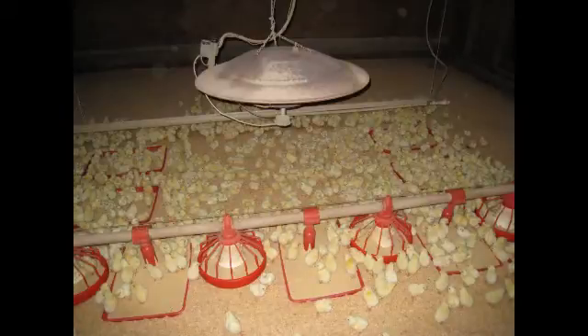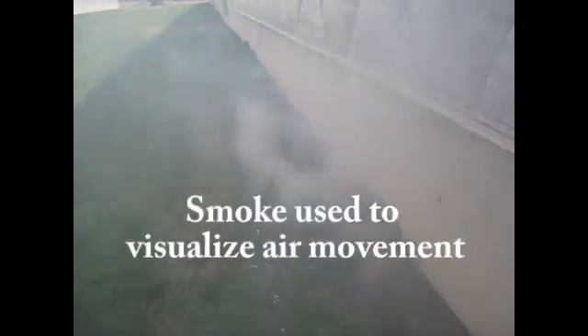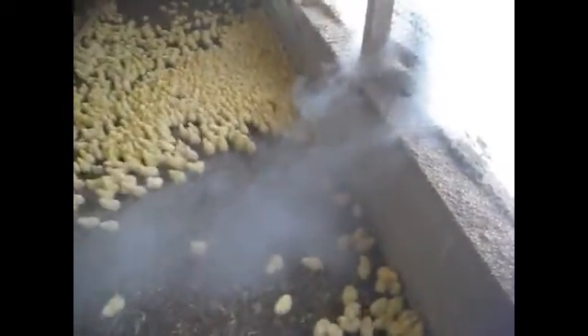Now let's talk more about why poultry house tightness is so important. When the building is in heating or brooding mode, we only want heat to leave the building through the fans during a scheduled ventilation mode. Heat lost through building air leaks causes the heating system to run excessively and waste fuel. These leaks also allow cold, unconditioned outside air to enter the building freely and can cause chilling of the birds, non-uniform floor temperatures, and poor litter conditions.